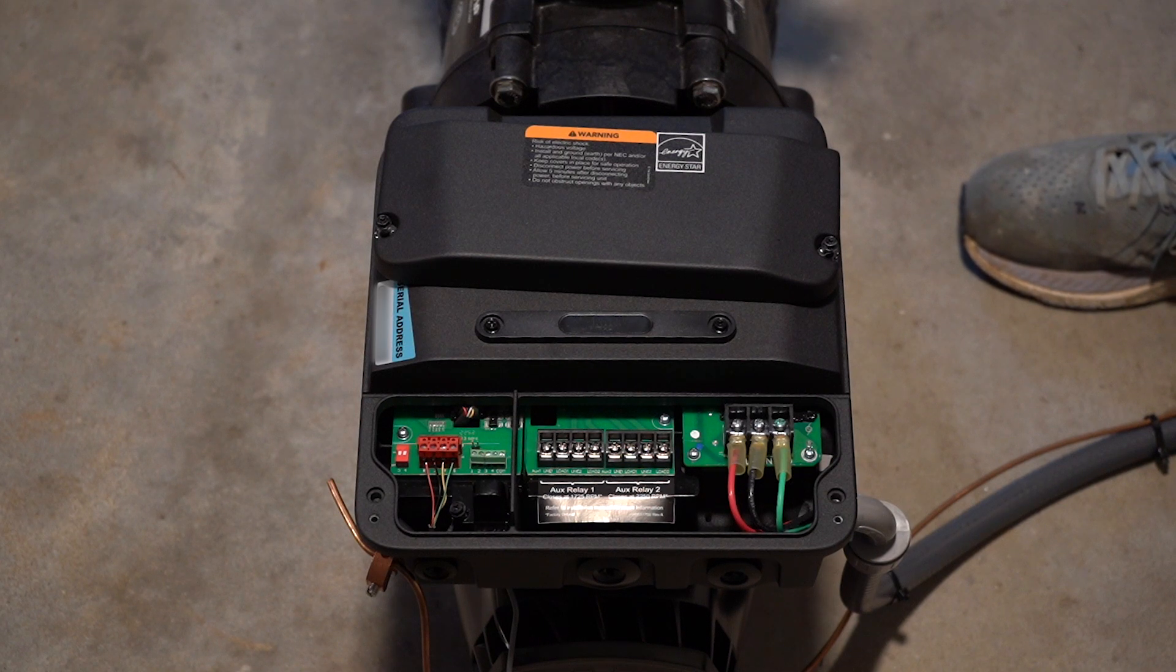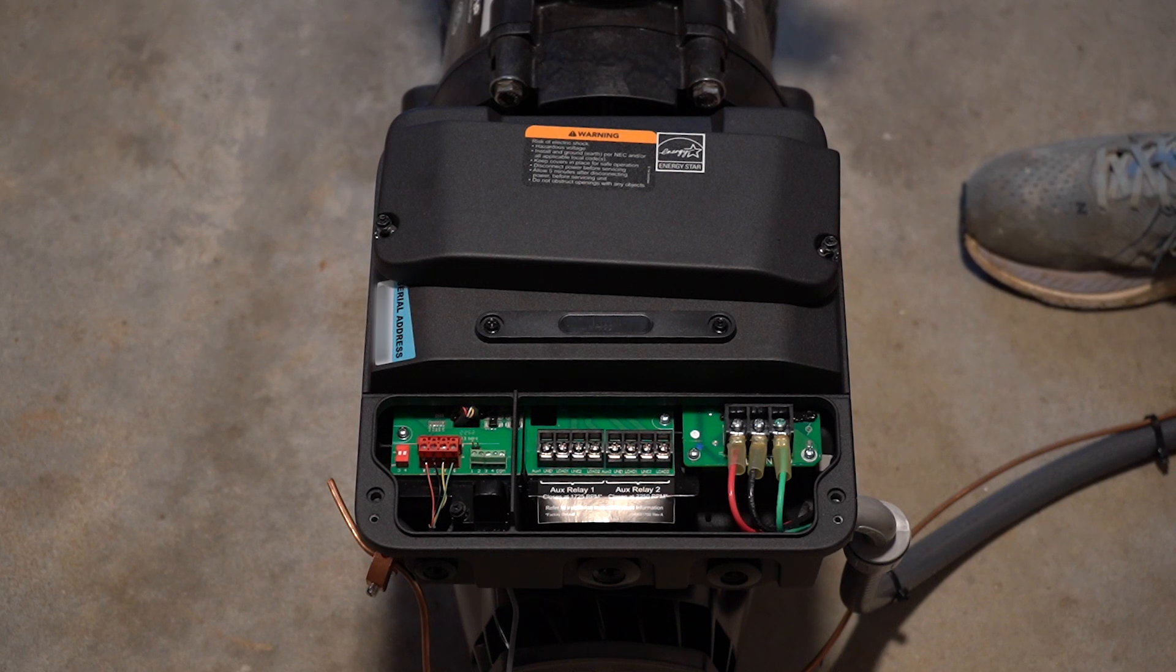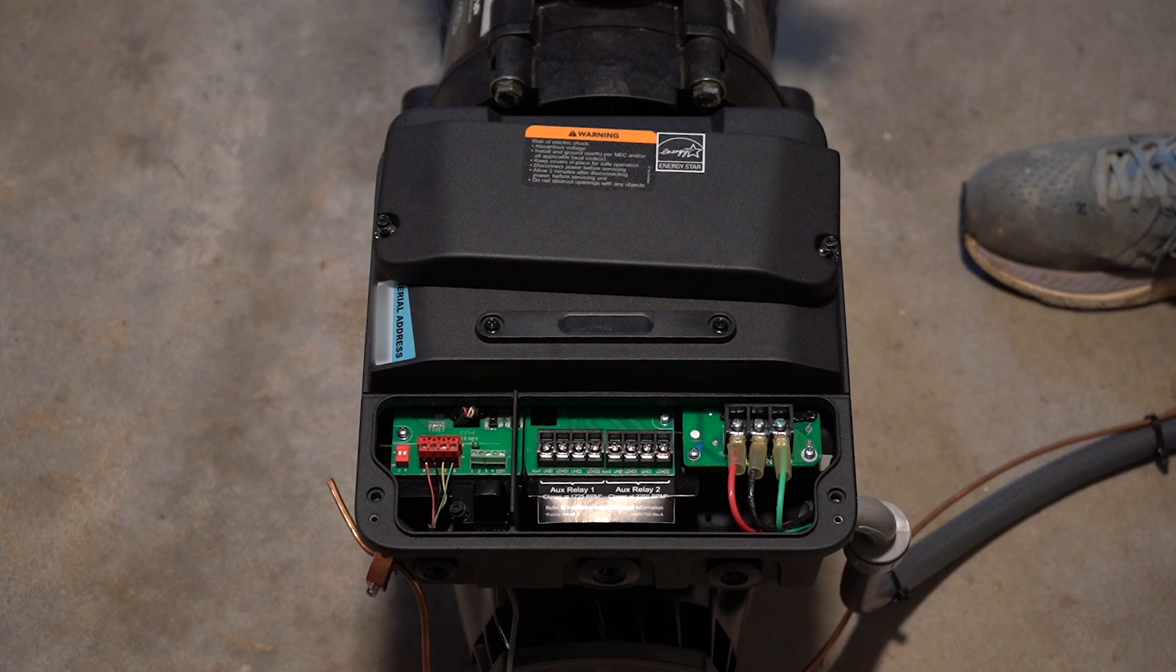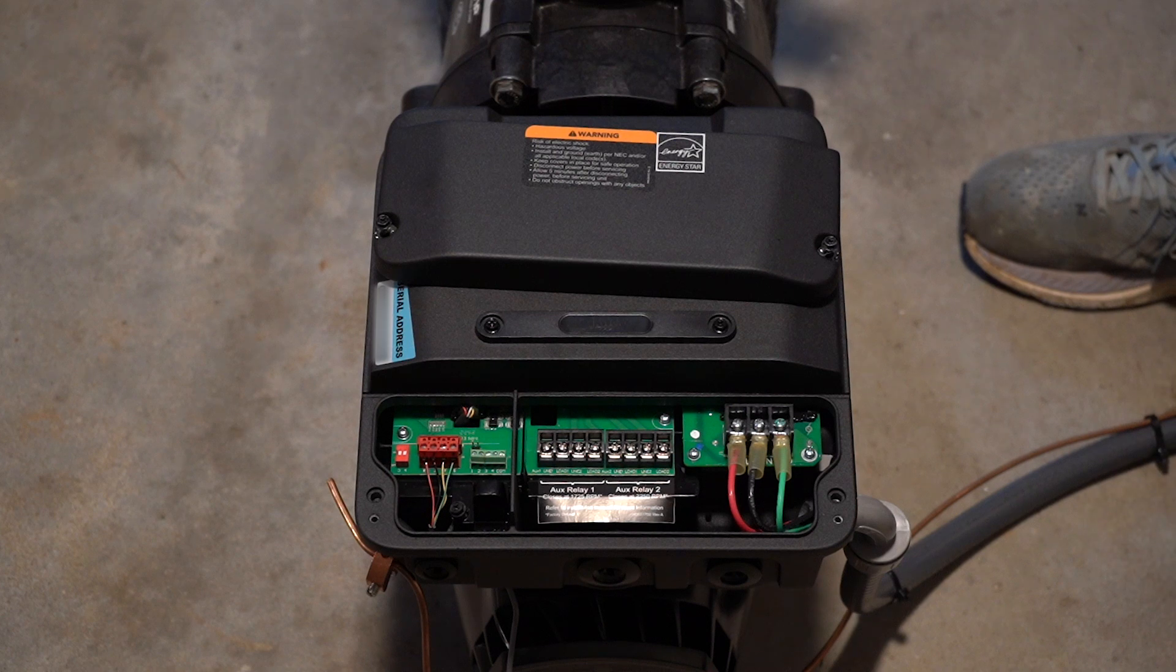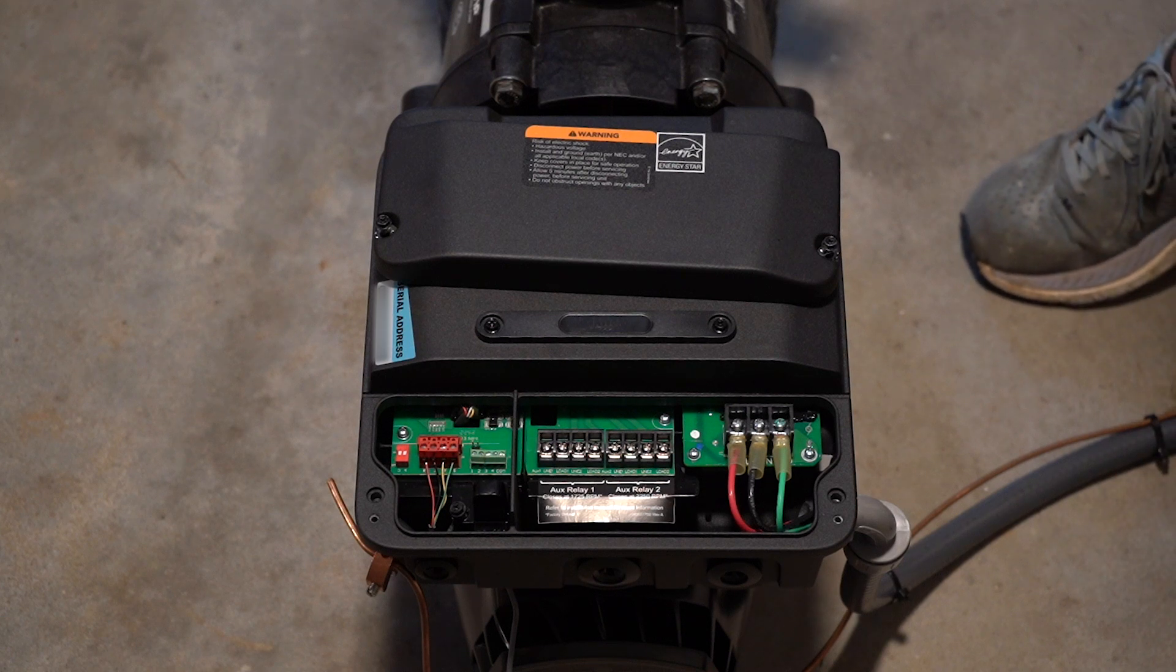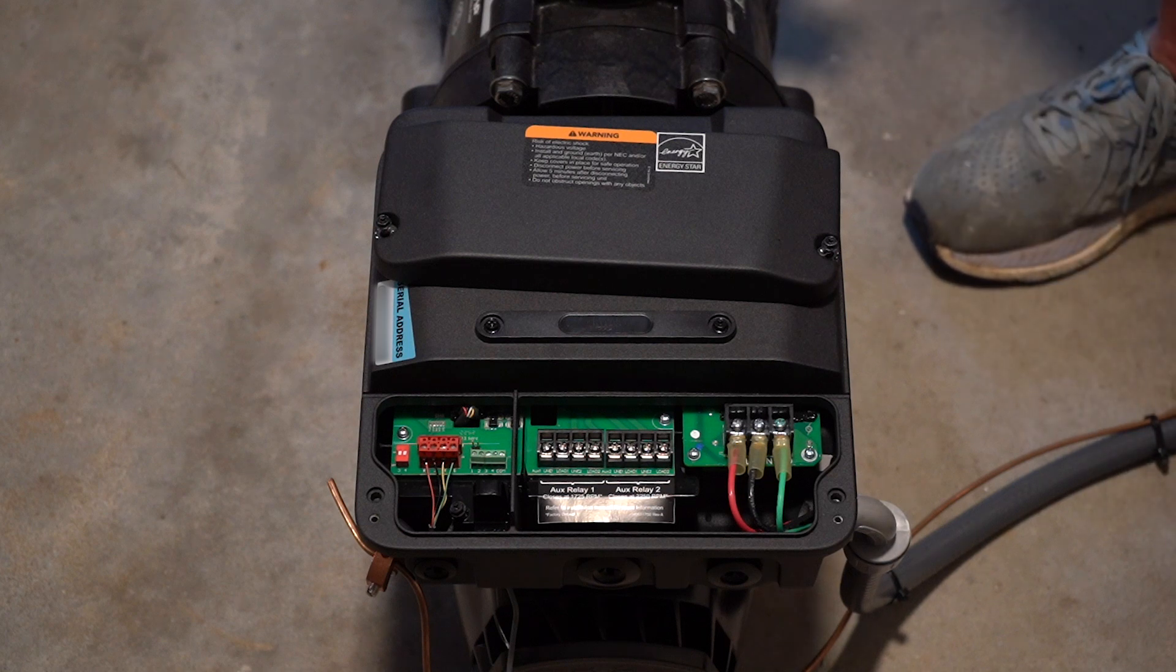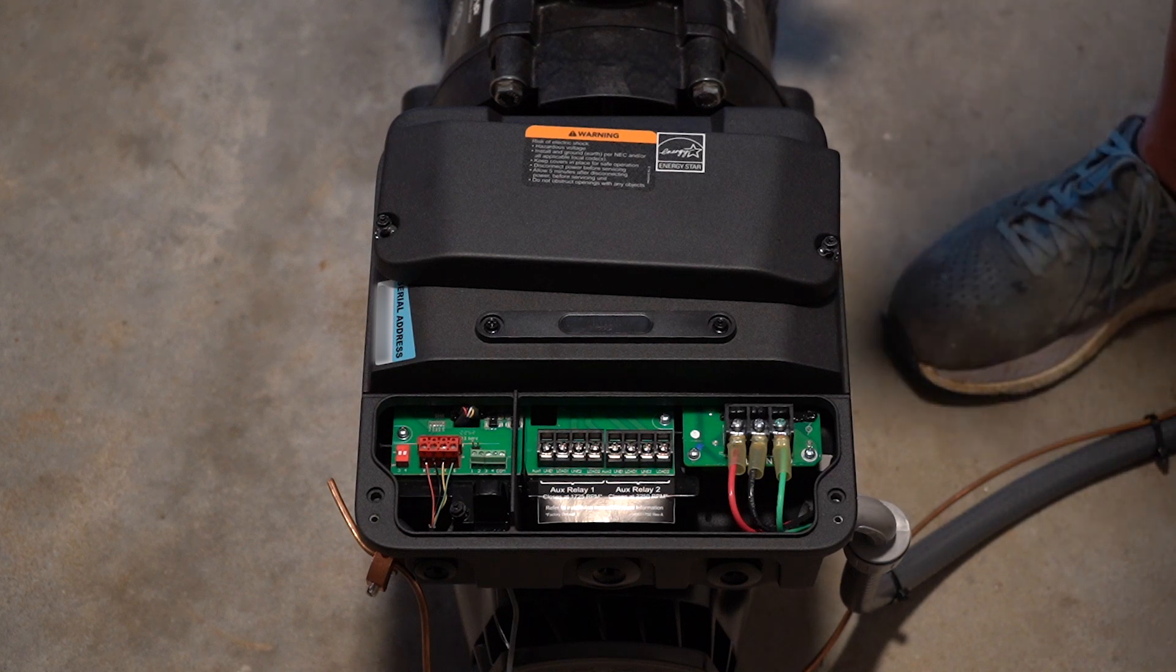But we're not going to use that. And if you have a newer system, you cannot set up using the legacy switches because it will cause a conflict. It'll eventually find this pump, it'll want to assign it, and then you'll have some issues with it turning on and off in what I call ghost mode.